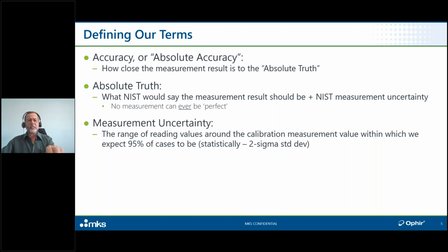Keep in mind that there's a difference between measurement uncertainty, which is the bottom line uncertainty that's specified in the data sheet of a measurement instrument, so that when you use it and you get a reading, that's the uncertainty level in your measurement, as opposed to calibration uncertainty, which is the uncertainty in our internal calibration process. That's something that's invisible to you, not the value. We publish the value, but the calibration process is something that happens in our calibration labs. It happens before the instrument got shipped out the door. What interests you is the bottom line uncertainty that you can expect when you're using it. We provide in our data sheets both numbers, but these are two different numbers. And we'll bump into that again in a couple of minutes.